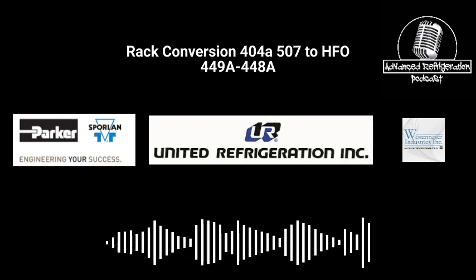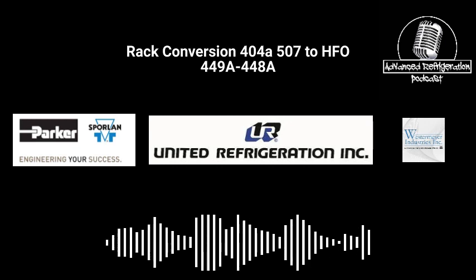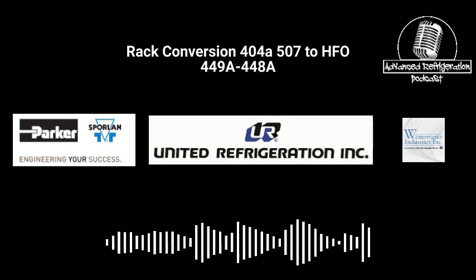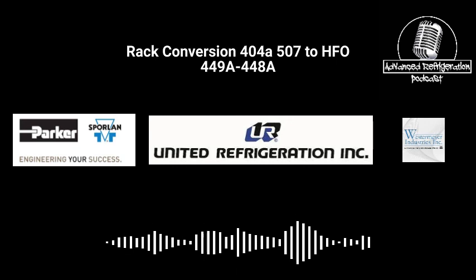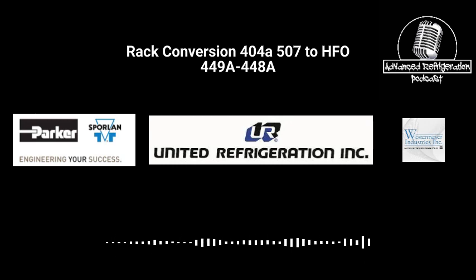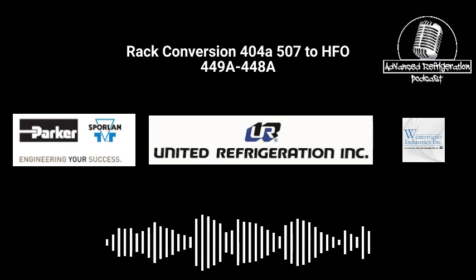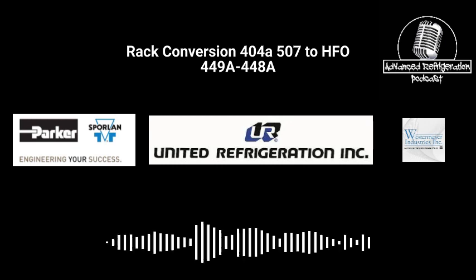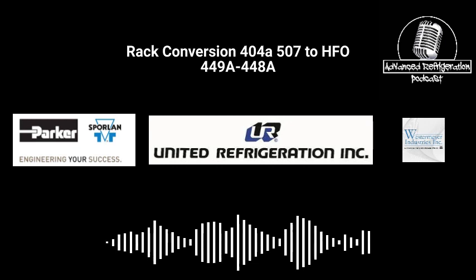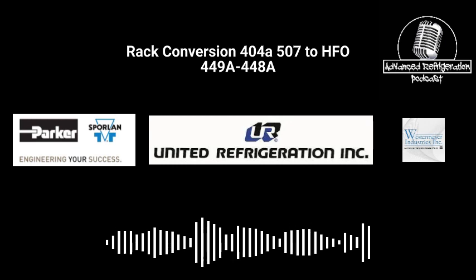So getting the power heads done, you want to get them done before. I'm a big proponent of doing them before. It's too stressful having that many people mess with that many power heads. You're just asking for a leak and pulling vacuums. Let's be honest, you're not getting down to 500 microns on a retrofit, you don't have time for that. Unless they're pulling all the food, you're gonna want to get that thing done. The night of the retrofit, I don't want to do anything besides pull the gas out, slam new liquid cores in there, pull a vacuum, and recharge it.